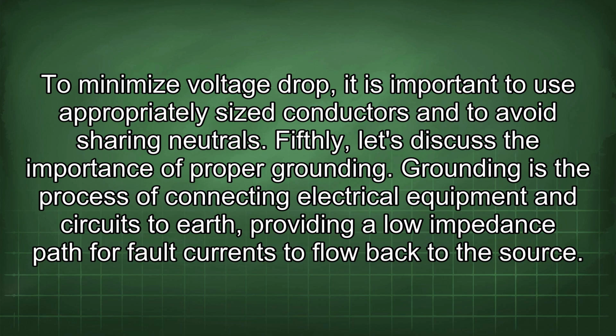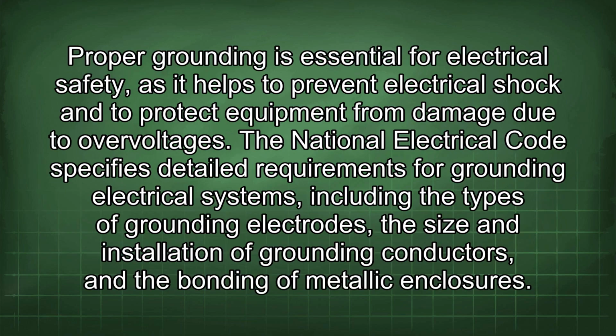Fifthly, let's discuss the importance of proper grounding. Grounding is the process of connecting electrical equipment and circuits to earth, providing a low impedance path for fault currents to flow back to the source. Proper grounding is essential for electrical safety, as it helps to prevent electrical shock and to protect equipment from damage due to overvoltages. The National Electrical Code specifies detailed requirements for grounding electrical systems, including the types of grounding electrodes, the size and installation of grounding conductors, and the bonding of metallic enclosures.